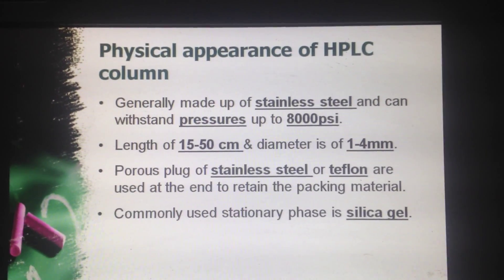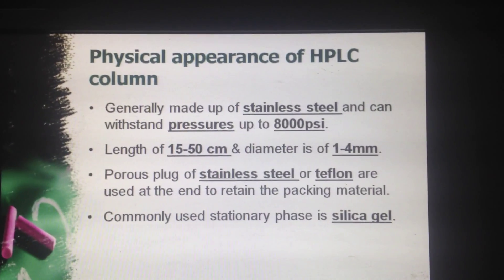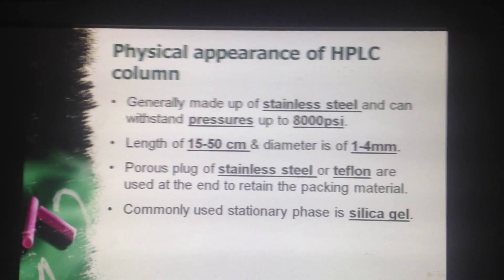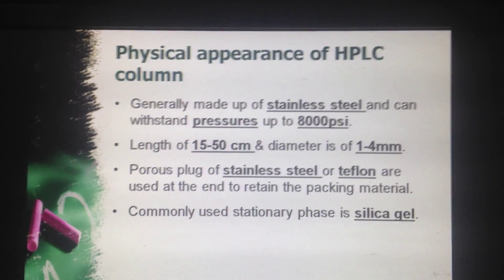Physical appearance of HPLC column: generally made up of stainless steel and can withstand pressure up to 8000 psi. Length is 15 to 50 cm and diameter is 1 to 4 mm. Porous plug of stainless steel or Teflon is used at the end to retain the packing material. The commonly used stationary phase is silica gel.